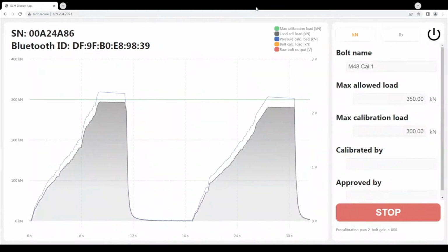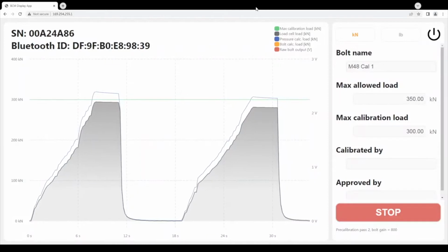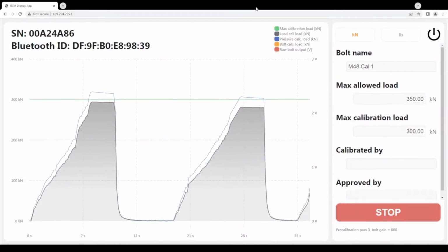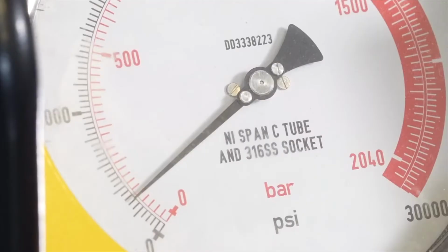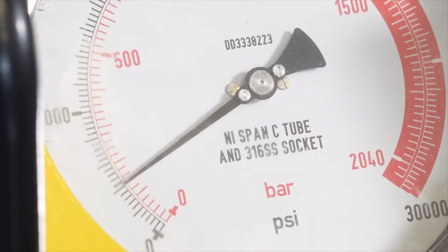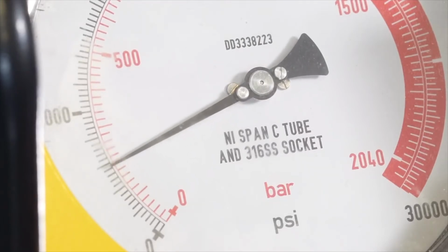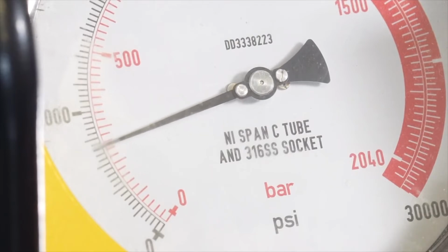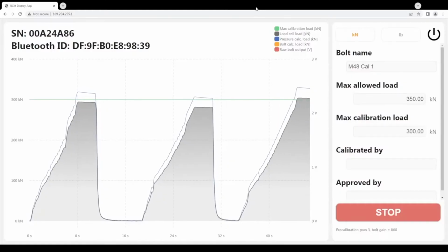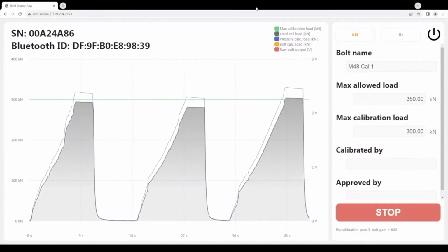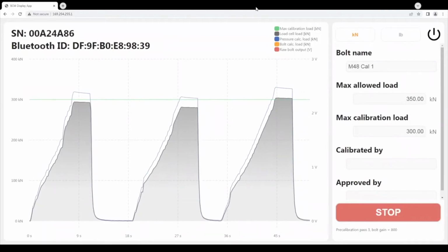All of the pressure application, dwelling, reading, controlling the pump, reading the pressure from the pressure transducer, and reading the load from the calibrated load cell is done fully automatically. So this is the end of the 3rd shake. After the 3 shakes, we are ready to proceed with the final calibration.